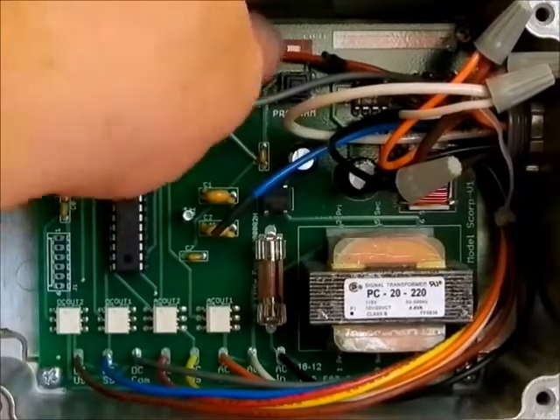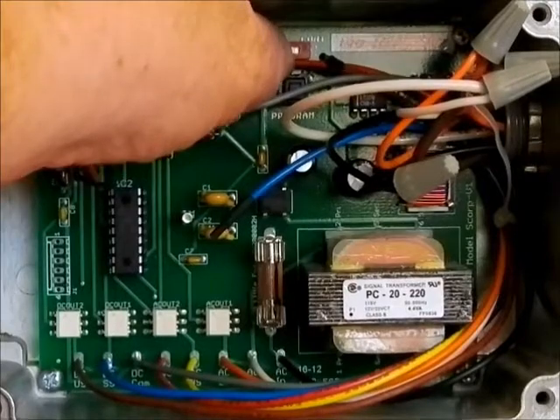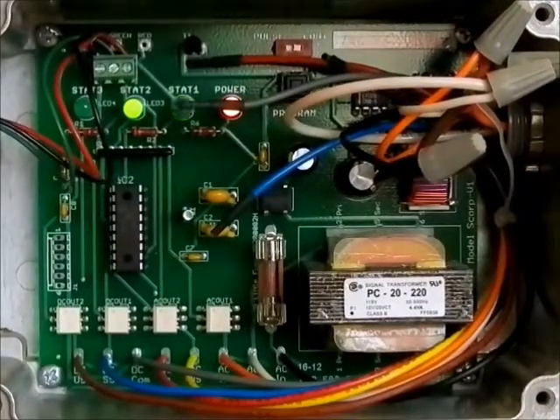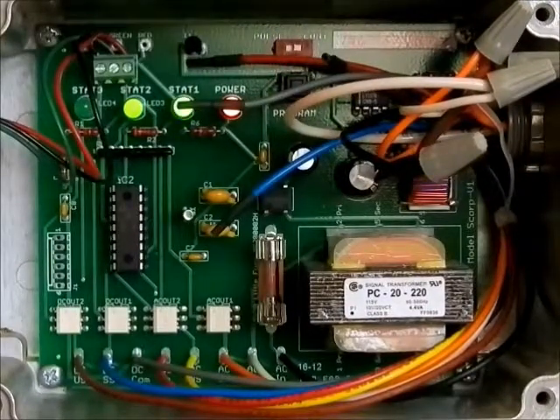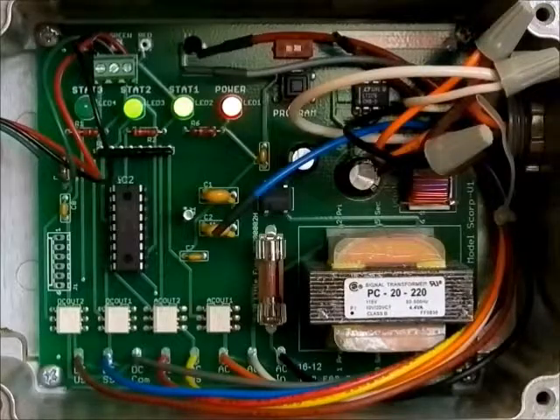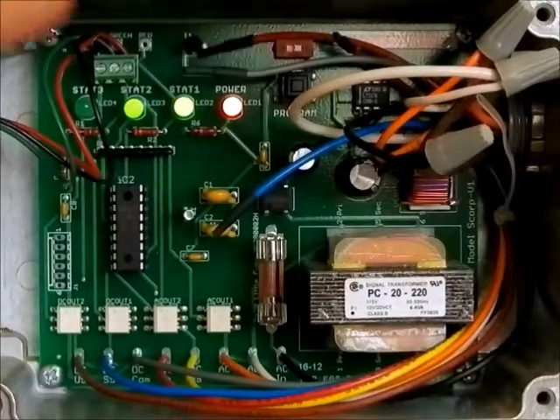There is a small slide switch inside the SC1 that selects either pulsed or continuous output for the speed switch signal. We will now set it to continuous output, and we can see the change to indicator STAT2. Likewise, the control tower will now see a continuous signal on the speed switch indicator. Back at the SC1, we are setting the slide switch back to the pulse position.